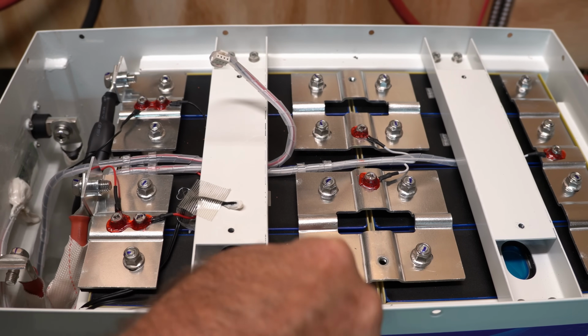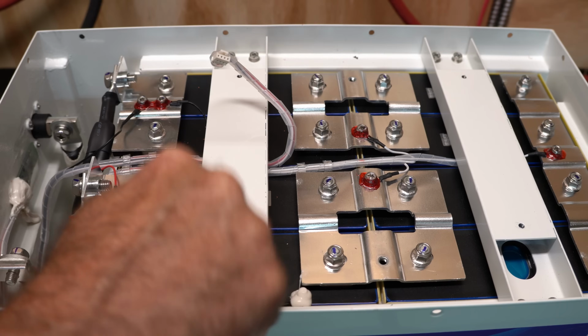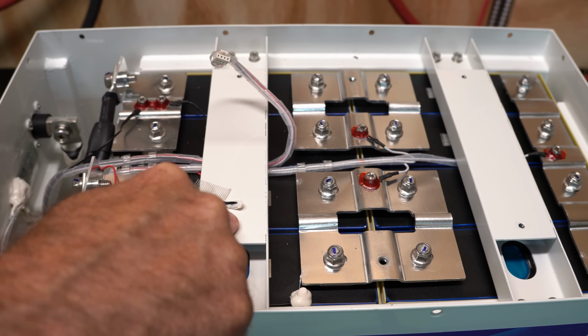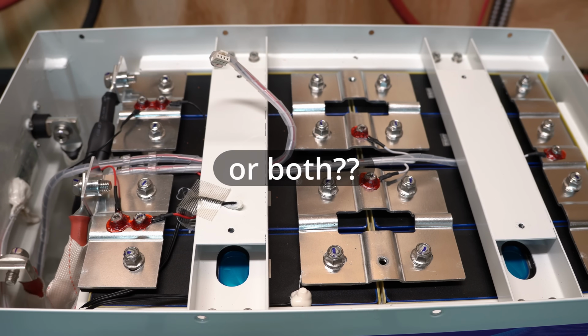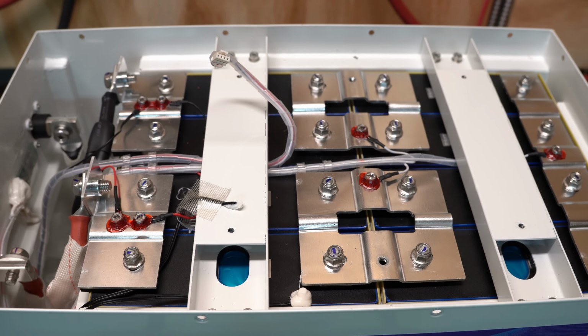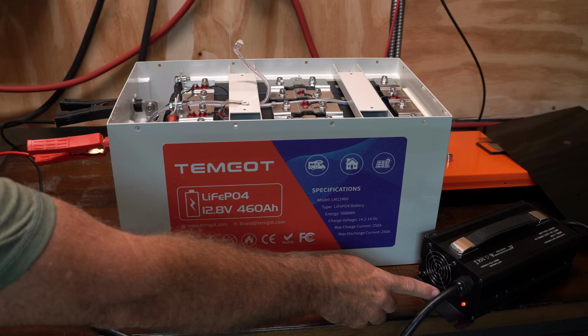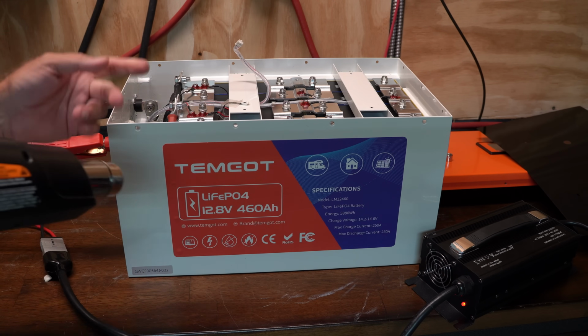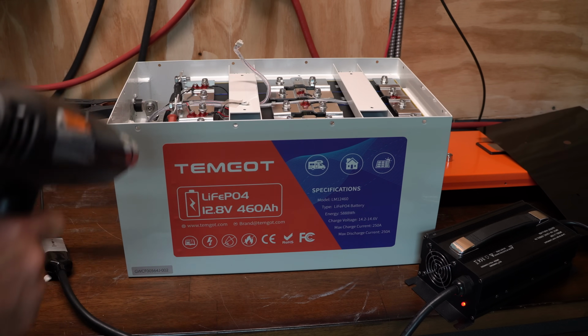Let's see if we can find where the other one goes. Oh, okay, so the other temperature probe is over here. We're going to see if this is a low temp or high temp probe first, and see if it cuts off charging as we would expect. You can see down here in the corner, the light is red, so we are charging. Let me try heating this up a little bit and see if that does anything.